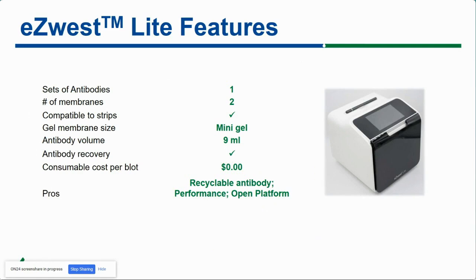Here are some more detailed numbers. This device will take one set of antibodies — one primary antibody and one secondary antibody — but it can process two membranes at the same time. You place both of them in the cassette and process them simultaneously. You can also use strips if you want to cut your membrane into smaller pieces. The device fits mini gels; a MIDI cassette is coming soon. For antibody volumes, for primary and secondary, you need about nine mils of diluted antibody, and then you can recover them.